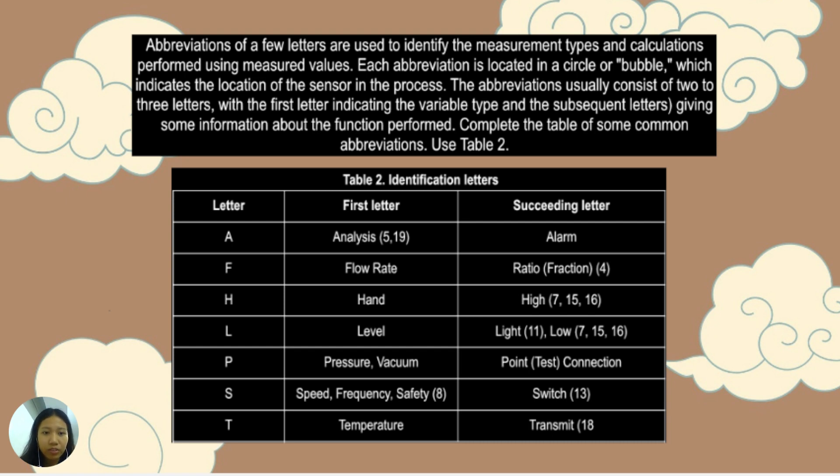For the identification letters. Letter A, for the first letter, it is analysis (5,19), succeeding letter alarm. F, flow rate, succeeding letter ratio, fraction (4). H first letter hand, succeeding letter high, 7, 15, 16. L, level, and for succeeding letter light (11), low 7, 15, 16. P, pressure or vacuum, and then for the succeeding letter point test connection. S, first letter speed, frequency, safety, and succeeding letter switch. And lastly, T, first letter temperature, and for the succeeding letter transmit.